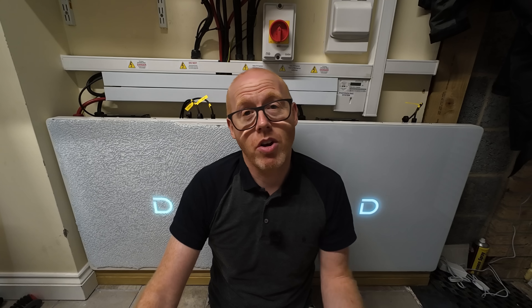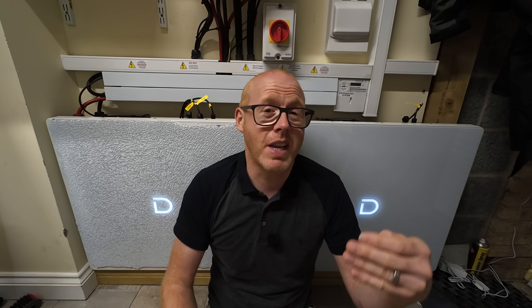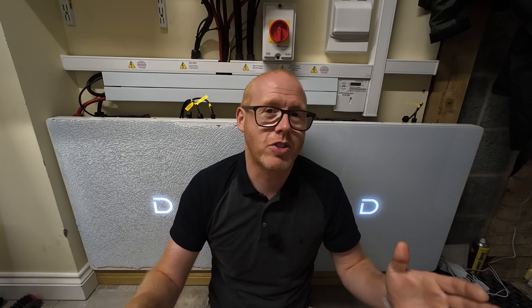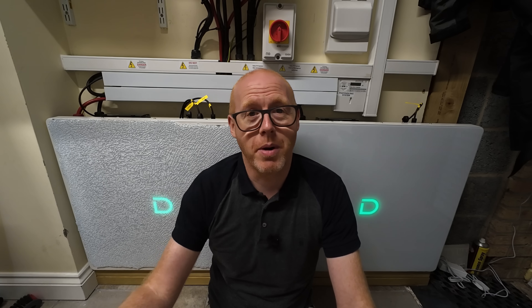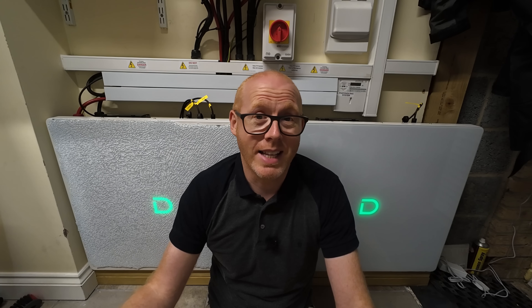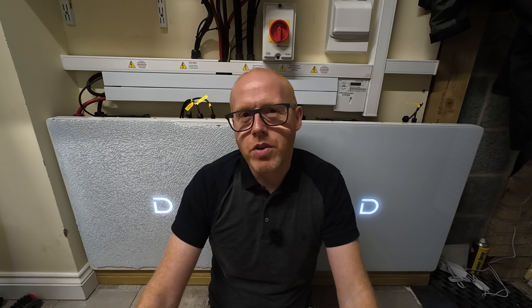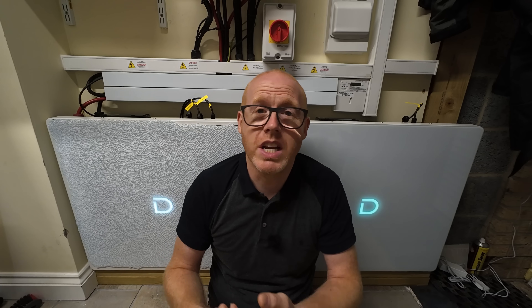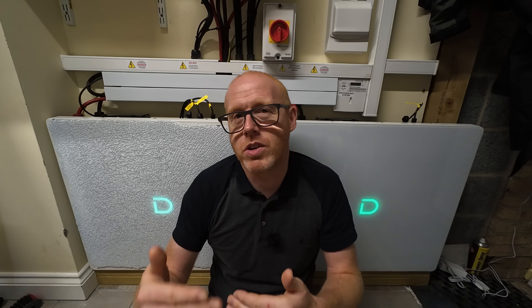The Fogstar batteries also had a specific weakness: the depth of discharge. There are some versions that have been improved — some have different BMS systems and firmware allowing varying levels of depth of discharge, so I don't want to make a blanket statement. I believe they have some products that do 90% now. But at the time, you were looking at buying a 15 kilowatt-hour battery and in reality you could not access three or more kilowatt-hours of that storage. Their warranty also had some question marks — it didn't cover as many cycle lives as most, with some Fogstar batteries only warranted for 3,000 cycles compared to the 6,000, 8,000, or 10,000 cycles offered elsewhere.